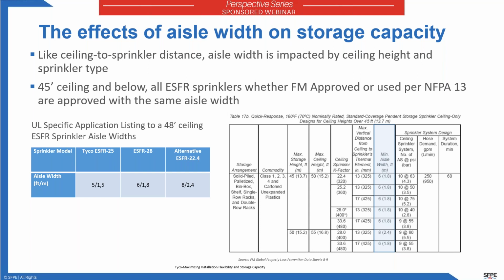The ESFR 28 is listed with a 6-foot aisle, and there's an ESFR 22 that also has the UL specific application listing, and that has an 8-foot aisle. So again, even though the sprinklers are approved to be used at a 48-foot ceiling, and even though, as I mentioned earlier, these same 3 sprinklers have the same ceiling to deflector distance of 14 inches, now they have different aisle width allowances, which is again critical to ensure that you're using the product correctly.